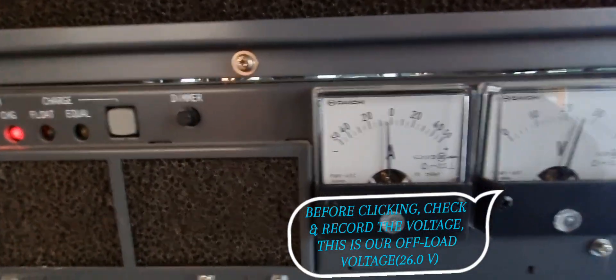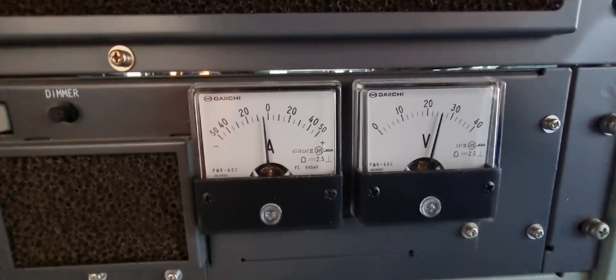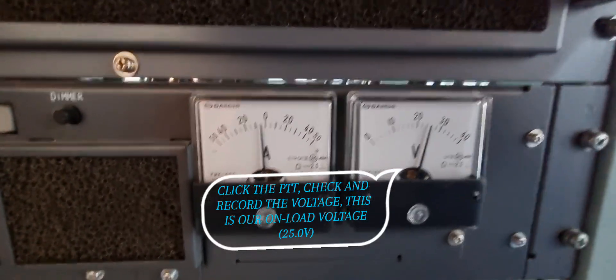Before clicking, check and record the voltage — this is our offload voltage: 26.0 volts. Click the PTT, then check and record the voltage — this is our on-load voltage: 25.0 volts.